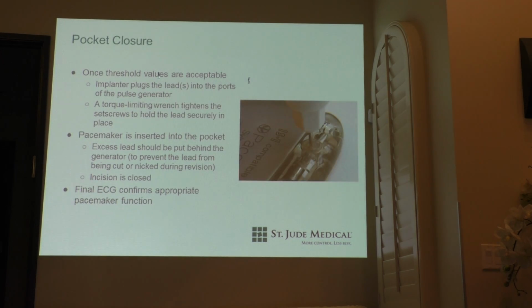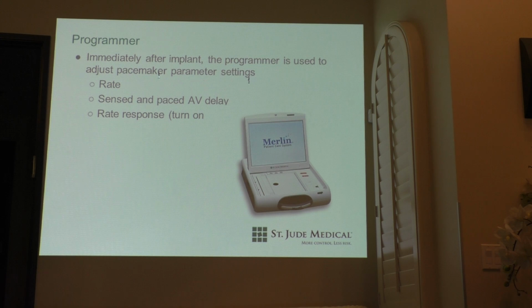All right, so you screw in, you connect, and then they close the pocket. While all of this is done, we're using the programmer to communicate with the pacemaker, because there's a wireless connection now on all of our devices that we're putting in. By and large, all ICDs out there and a lot of pacemakers have wireless communication, which means we don't even have to put a wand over the sterile field. You can do all this wirelessly. We continue to watch what the rhythm looks like beat by beat. We continue to test the lead to make sure that there haven't been any acute changes in the stimulation threshold, or that we've got bad sensing.